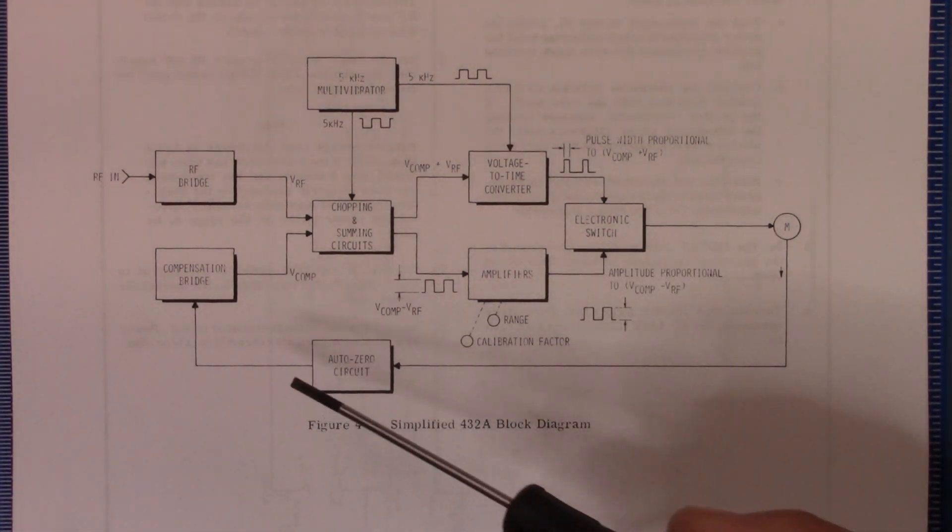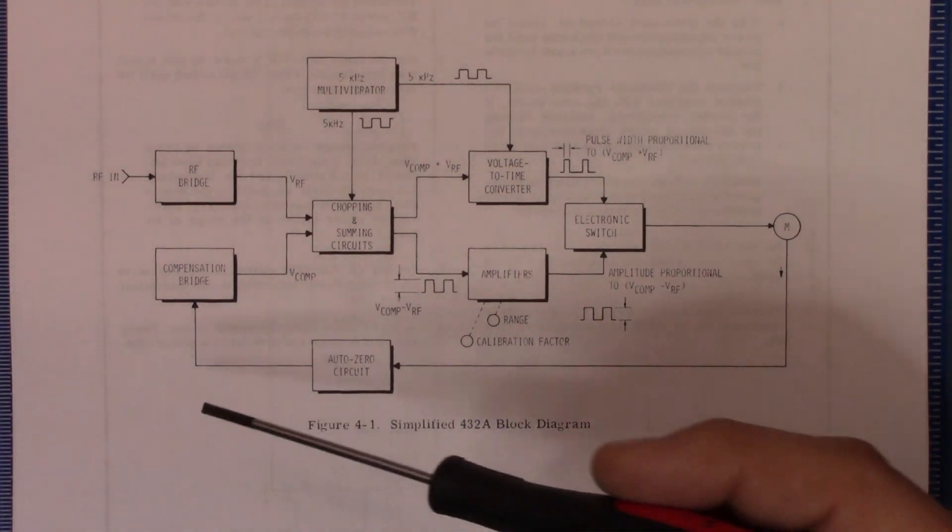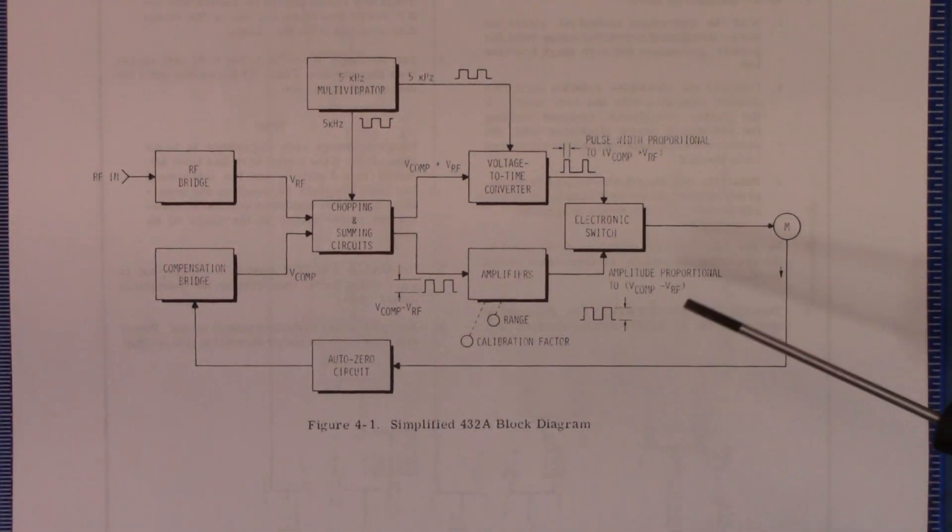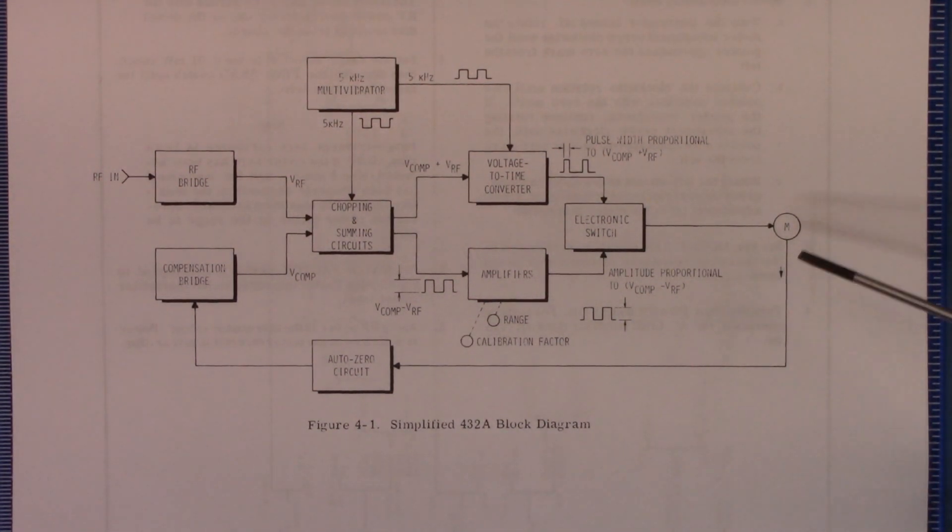They have one which is exposed to the RF energy and then one which is a compensation mount, which is picking up basically the ambient temperature and it's isolated from the incoming RF. That way, what the system can do is basically add together and subtract the effect from the temperature that the environment is in. So you get a signal on the meter that is proportional to the incoming RF power.